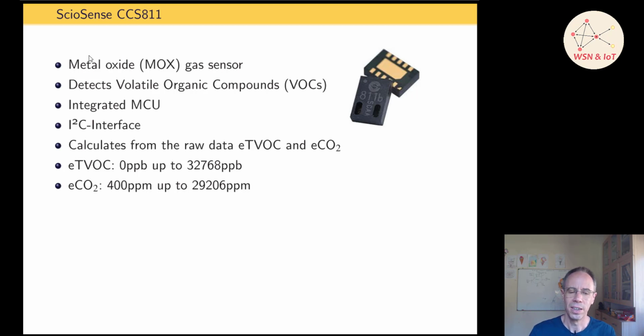It measures volatile organic compounds, and also gives a carbon dioxide equivalent. So it's actually related to the volatile organic compounds. These sensors can only give you a direction for the carbon dioxide level. From our tests, it wasn't really accurate, but you can at least get a direction of where the carbon dioxide is going. It's a metal oxide gas sensor, and I don't have very good experience with them. They are all not so accurate until now.